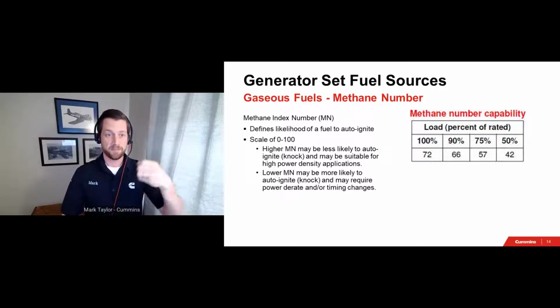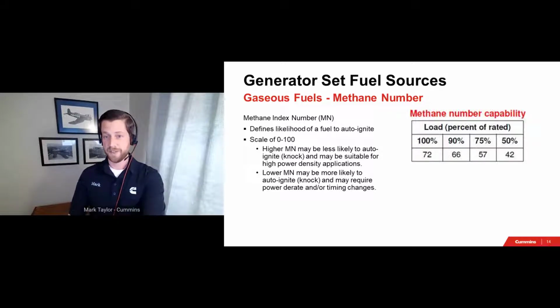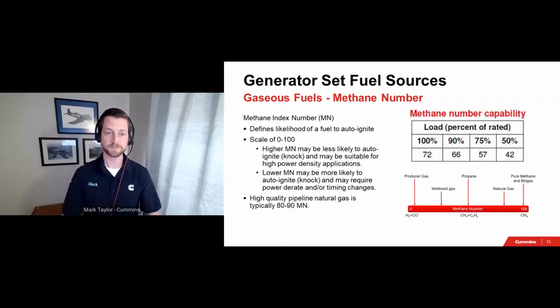Let's say the methane index number cannot exceed 57 per a fuel analysis, and the on-site fuel is measured to be 57 methane. We'll be looking at a max available power of 75% of the nameplate rating of the generator set to achieve best performance. Generally speaking, a fuel analysis of pipeline natural gas will produce a nice and high methane index number, usually around 80 or even 90. And the graphic on the right seeks to show how the methane index number for pipeline natural gas compares to some other common fuels.